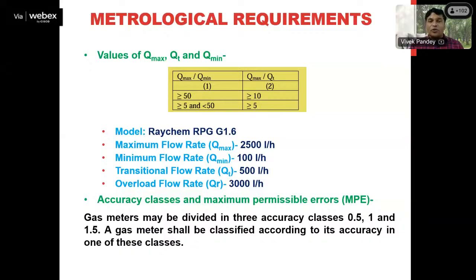In this same example, you can see another flow rate specified here, called the overload flow rate. I'll be talking about this flow rate in detail in the upcoming slides. But one thing you should know is that this overload flow rate is also specified by the manufacturer, and it should be 1.2 times Q max. In this case, 1.2 times 2500 is 3000 liter per hour. So it is correct. Fine. So the overload flow rate is also correctly specified here. What is the purpose of this flow rate, we will discuss later on.